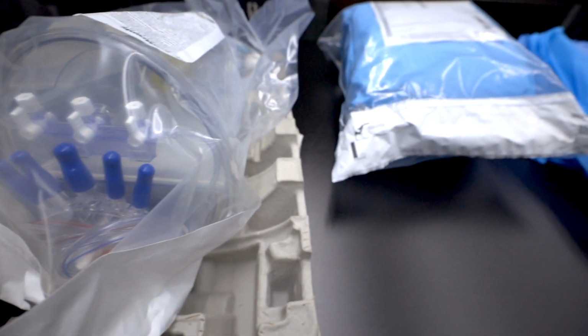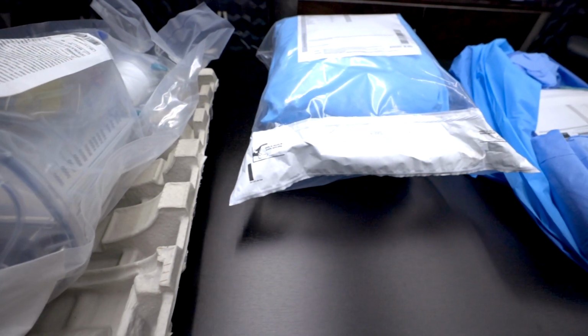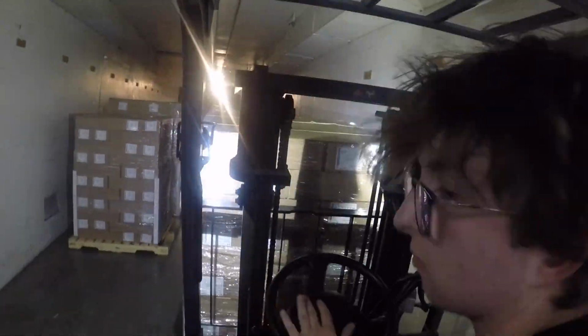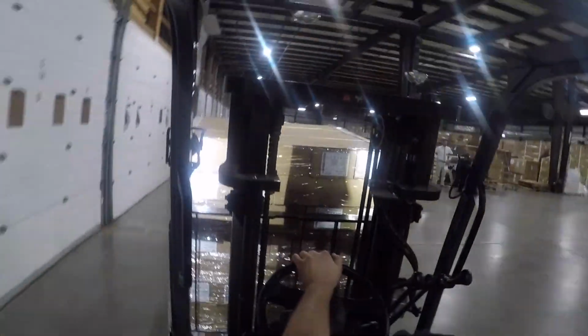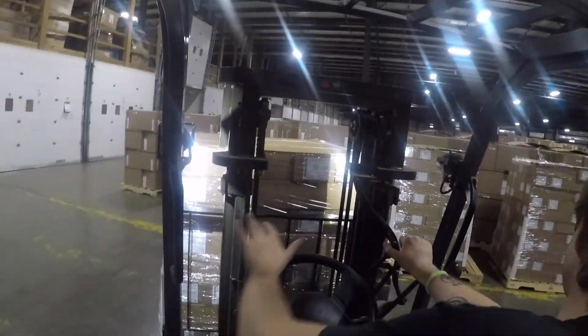With EO, we've got these trays that have all these different components. They're made from different materials, and they can all be sterilized with EO, but they can't be sterilized with other methods. The product that comes to Midwest Sterilization is going to come in its package, wrapped in a case, wrapped up, stacked up on a pallet, and it's going to go through the entire process looking just like that. So all cycles at Midwest are to be at exceptionally low levels of ethylene oxide or residual ethylene oxide.